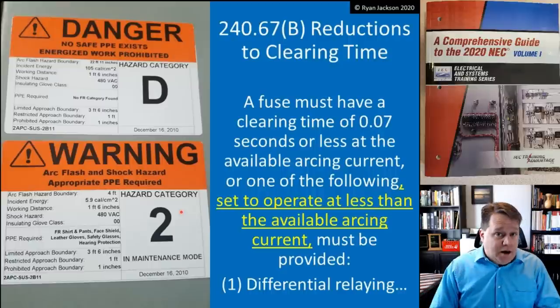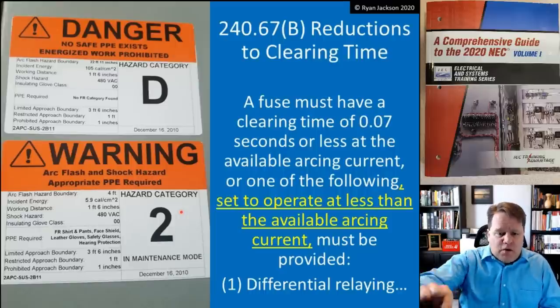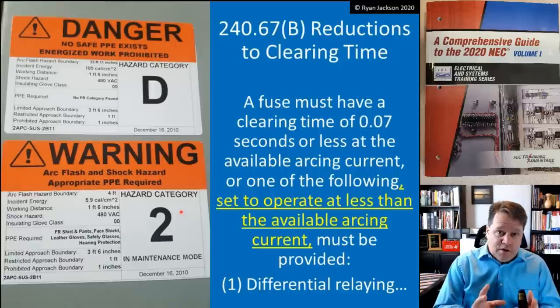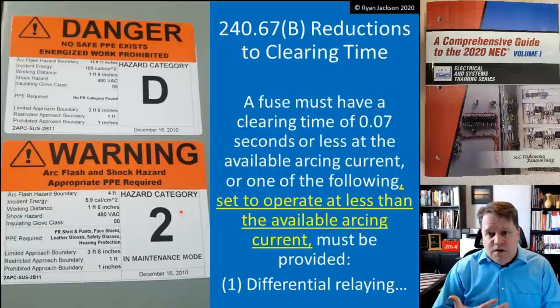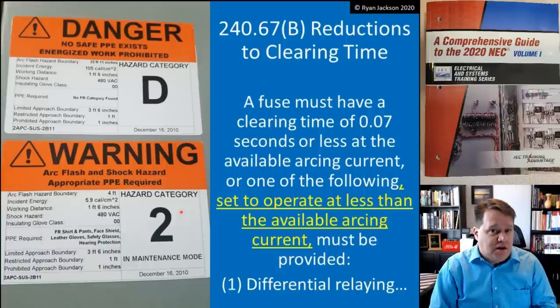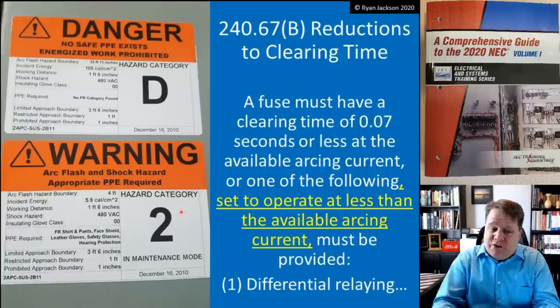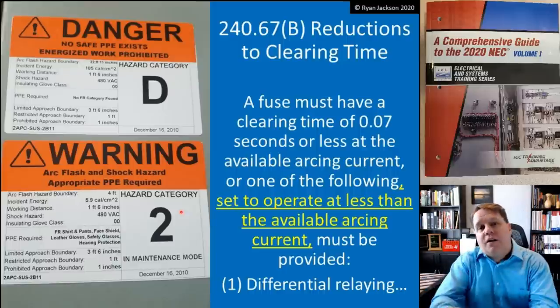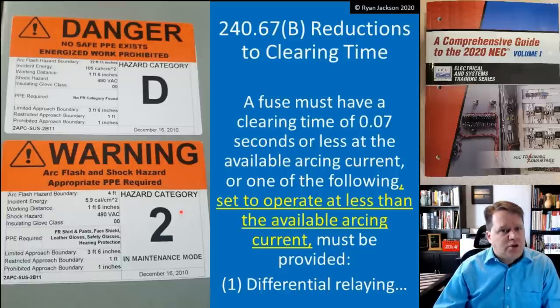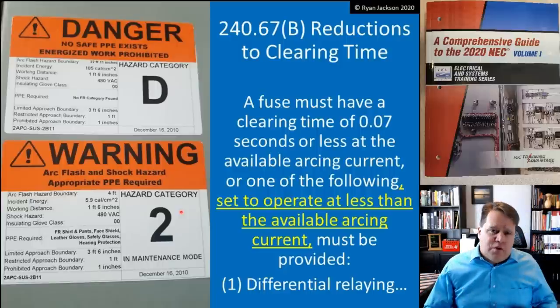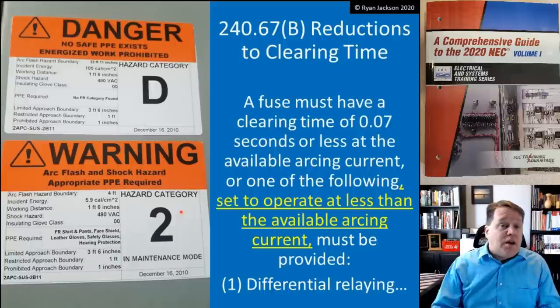That's a lot more comfortable than a 105-calorie spaceman outfit — and significantly safer. So when I hit the switch it reduces the clearing time, allowing me to do justified energized work such as measuring voltage or troubleshooting. I turn it to maintenance mode, reduce my risk substantially, then take it off maintenance mode when done.